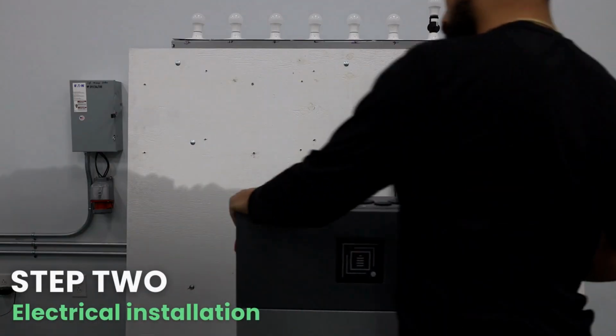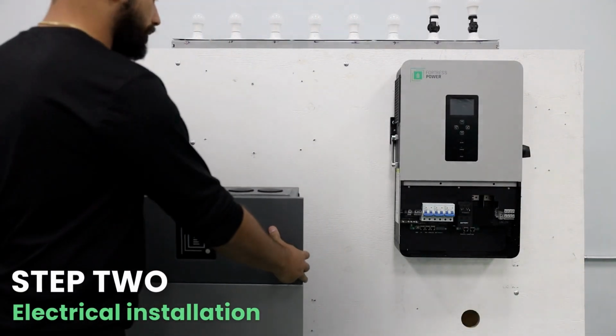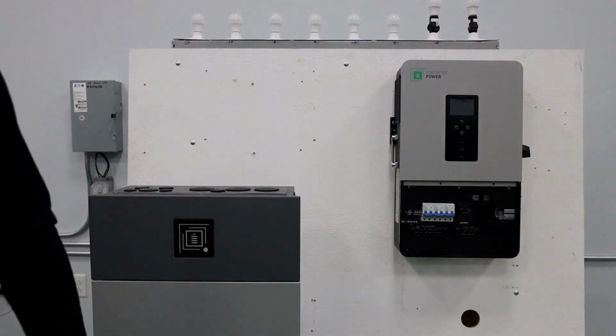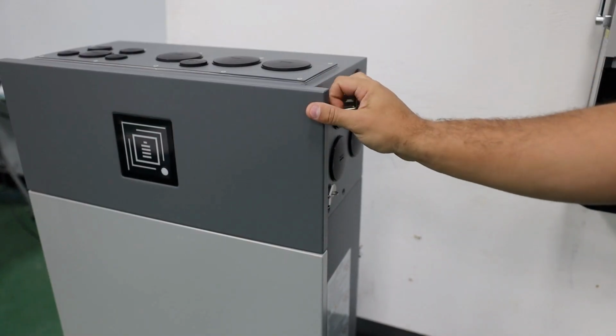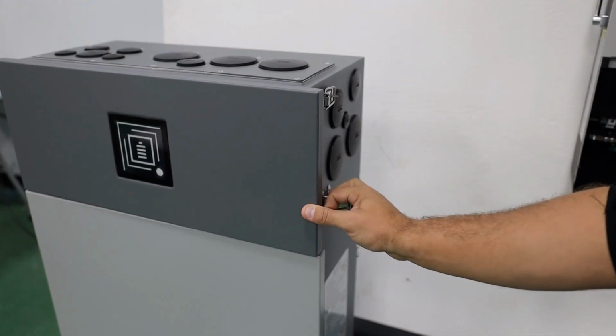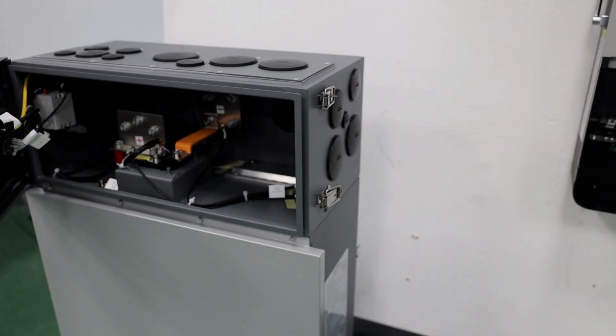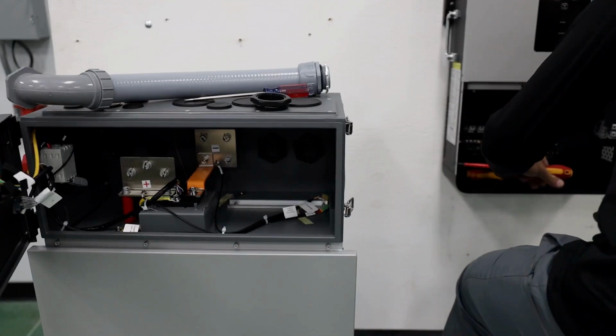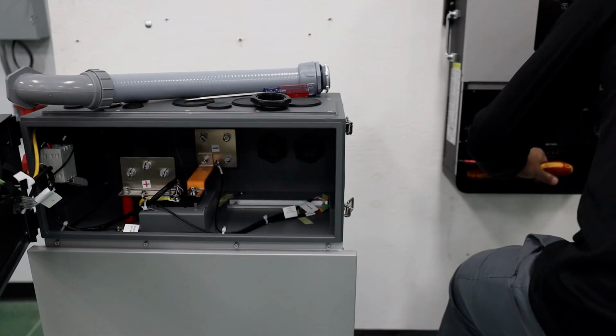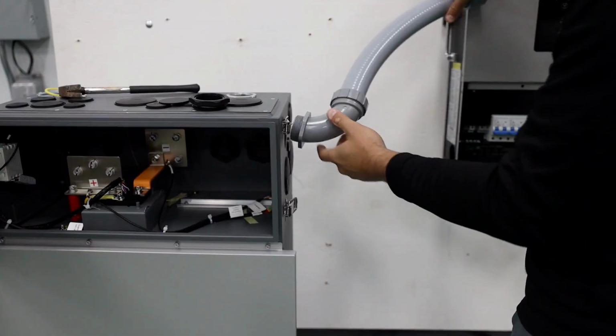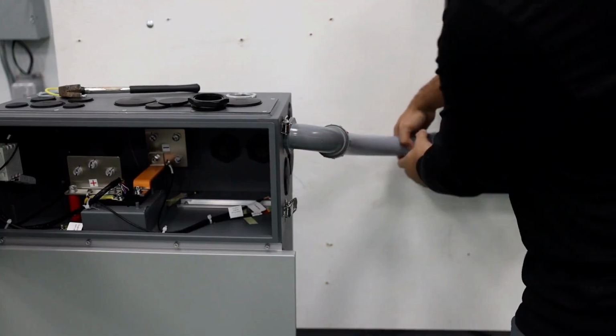For demonstration, we will be using a Fortress Power eBoost 16 kWh battery. Open the E-way compartment to access the battery busbar. Remove the knockout caps on both the battery side and inverter side, then install a 1.5-inch flexible or EMT conduit from the side of the E-way to the side of the solo inverter.